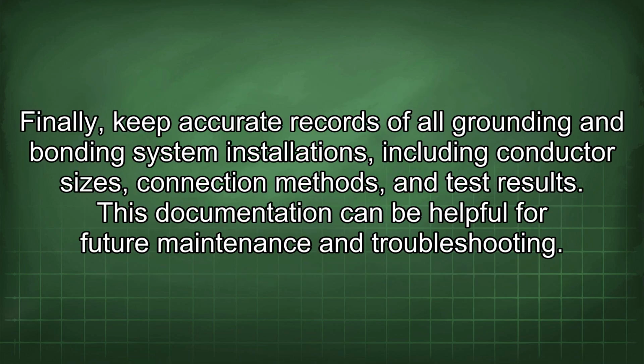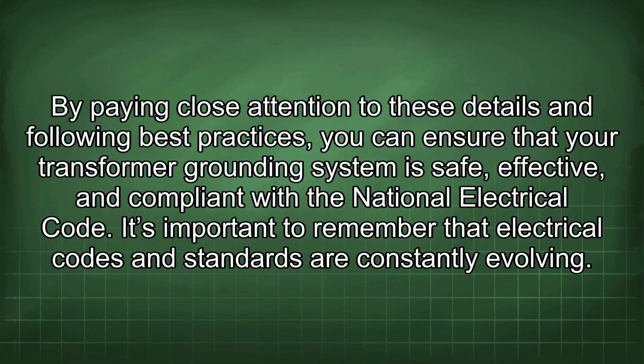Finally, keep accurate records of all grounding and bonding system installations, including conductor sizes, connection methods, and test results. This documentation can be helpful for future maintenance and troubleshooting. By paying close attention to these details and following best practices, you can ensure that your transformer grounding system is safe, effective, and compliant with the National Electrical Code.